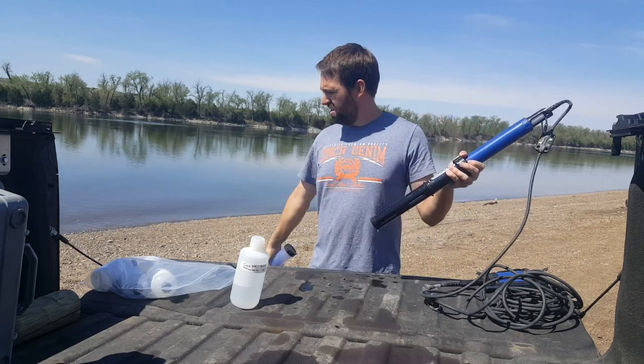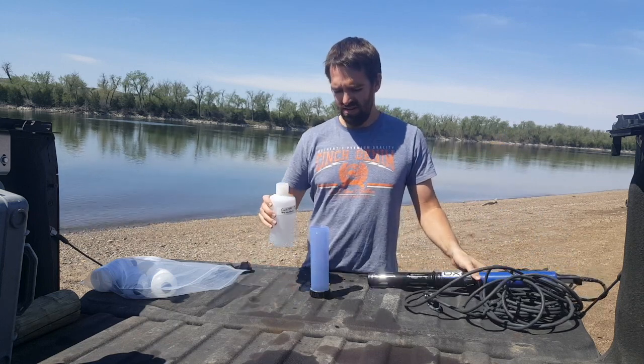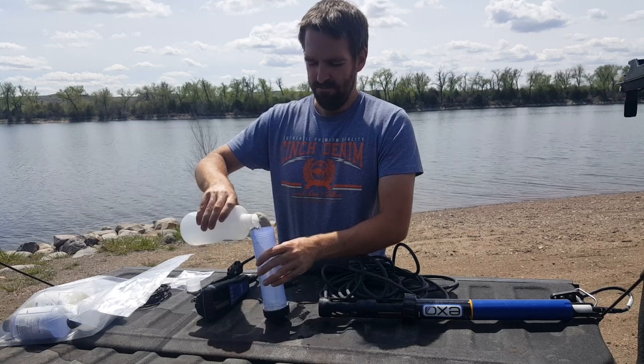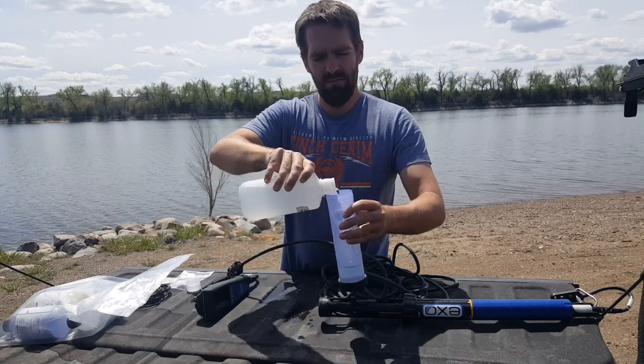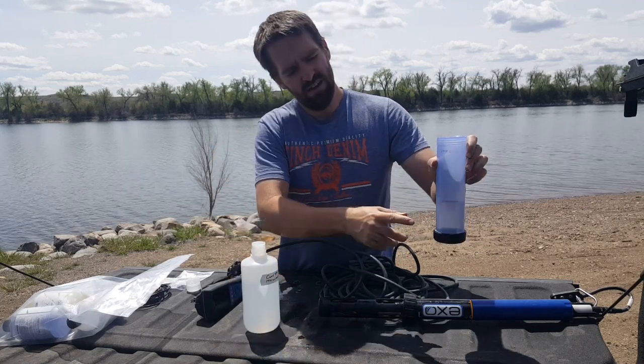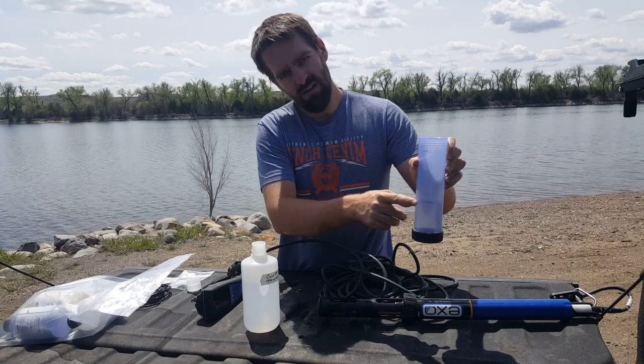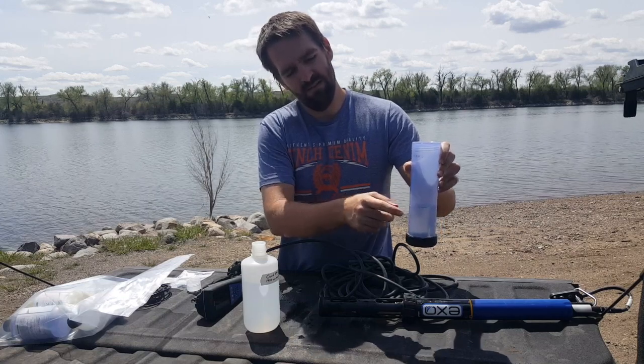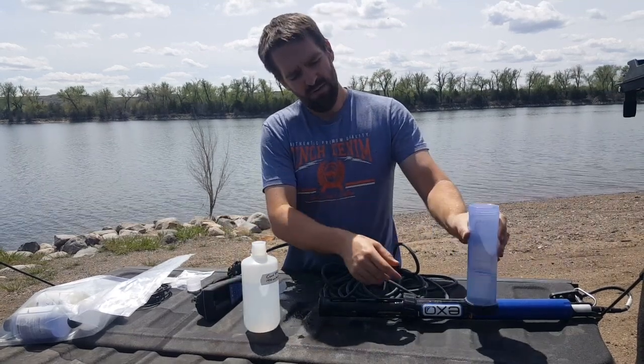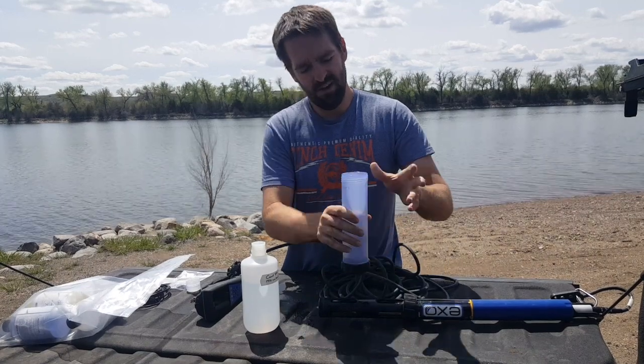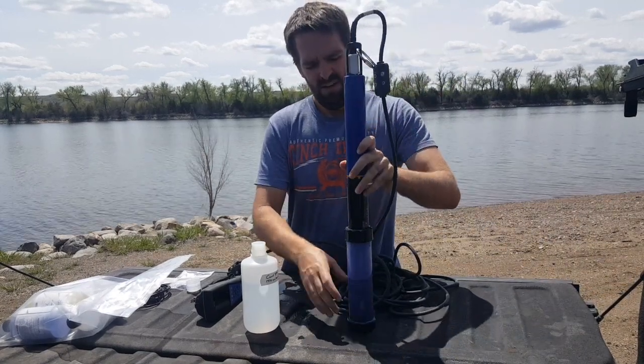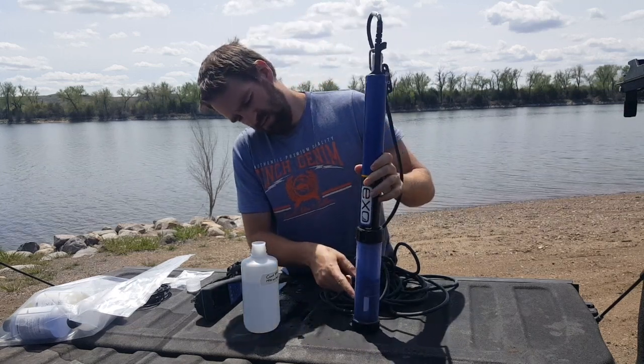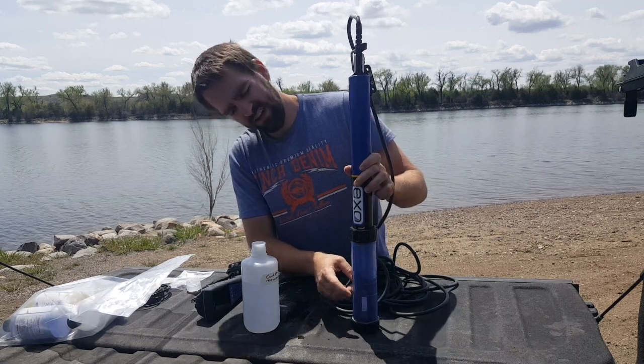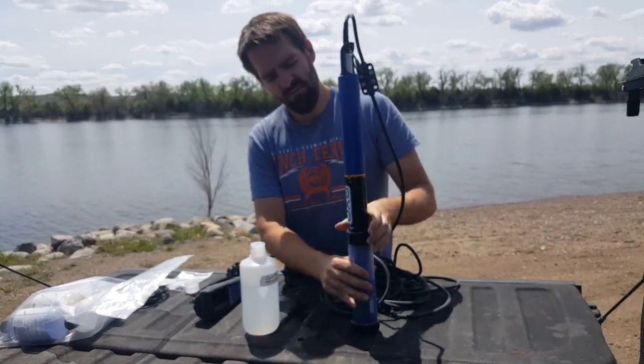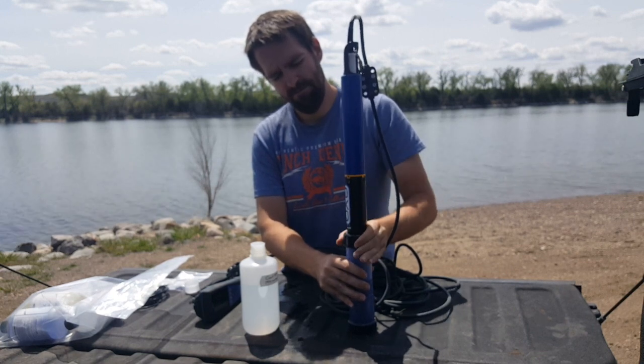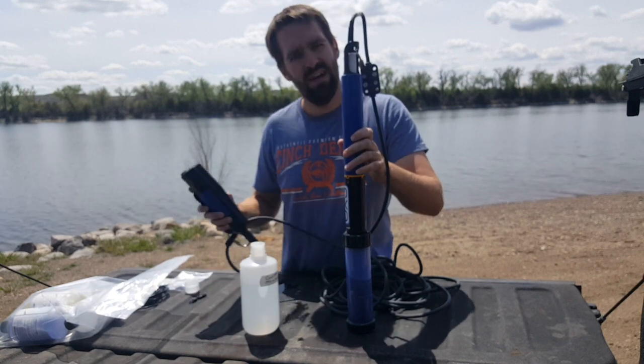We're then going to discharge a little bit of solution. So I'm going to fill my cup to just above the bottom line. You can see the cup has two lines. So you have your bottom line, this is your minimal fill line for calibrating, and then you have the top line, this is the maximum fill line. So I always fill the cup just above the bottom line. You shouldn't have to go any farther than that. The tip of our probe is submerged in the conductivity solution. So what I do is I'm going to tighten the cup, keep it vertical so the tip is still submerged in this conductivity solution, and we go to our handheld.